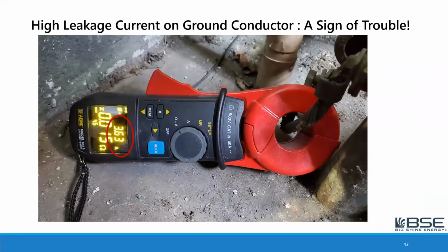I did mention earlier that one of the things we can do during a grounding survey is to test for leakage current on a ground conductor. Because really the ground conductor should not routinely have a lot of current passing on it. But here you can see our AEMC clamp meter around this braided, heavy copper grounding conductor, and it has almost 4 amperes of current on it. That's a sign of problems. It shouldn't be. If we see more than 1 amp, automatically we assume this is something that should be investigated.